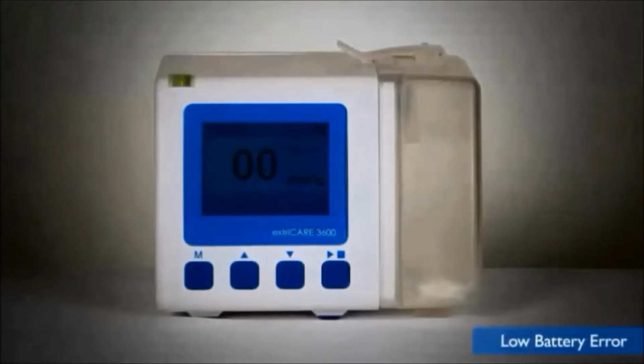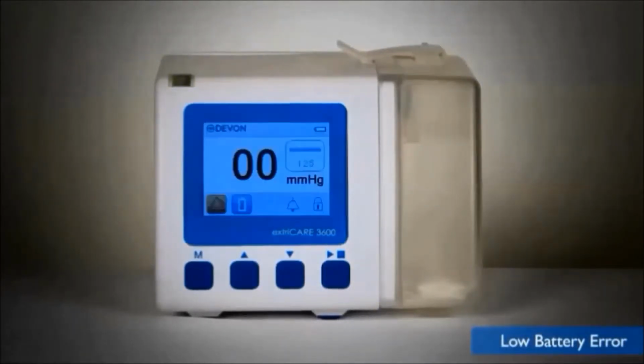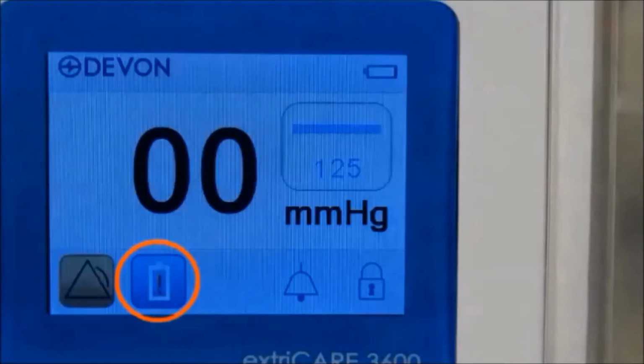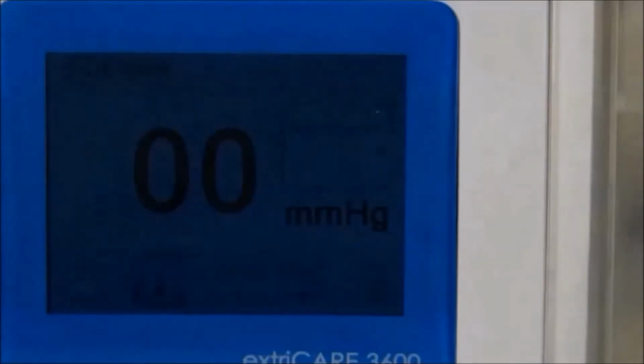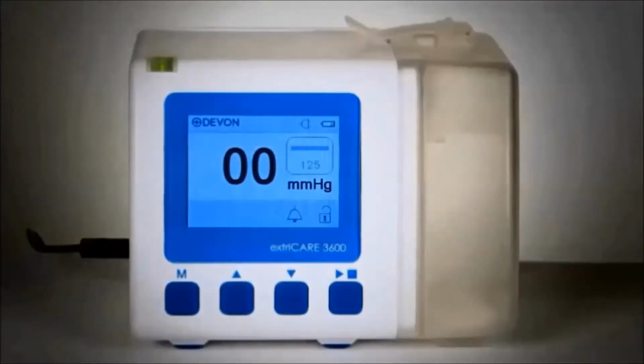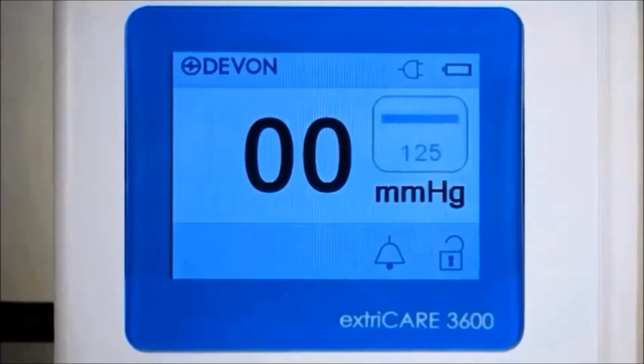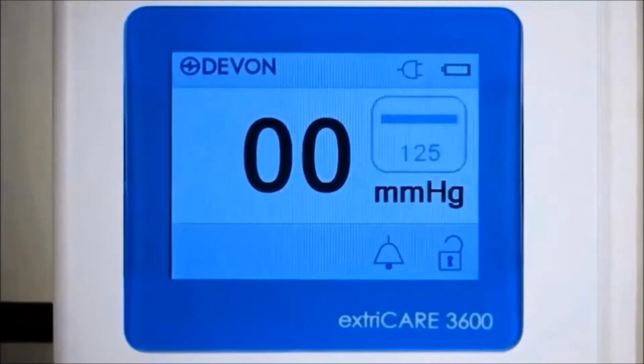Once there is less than 10% battery power remaining, an alarm will sound. The LED light will flash yellow and the low battery symbol will appear on screen. The pump will continue pumping until the battery is completely depleted. Plug in the extriCARE 3600 into a wall outlet to allow it to charge and function at the same time. The extriCARE 3600 will be fully charged after 5 hours.